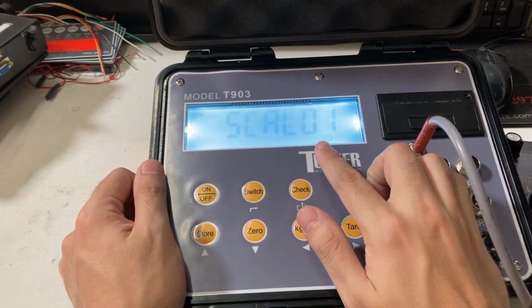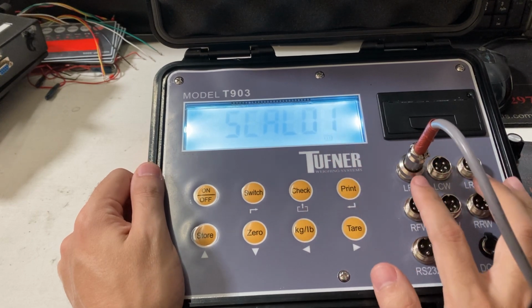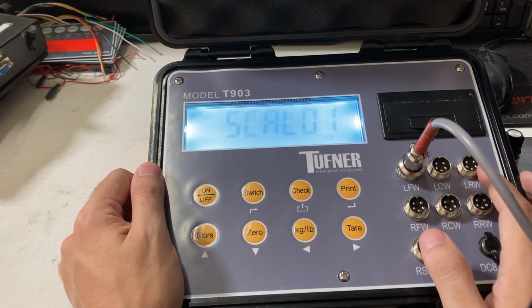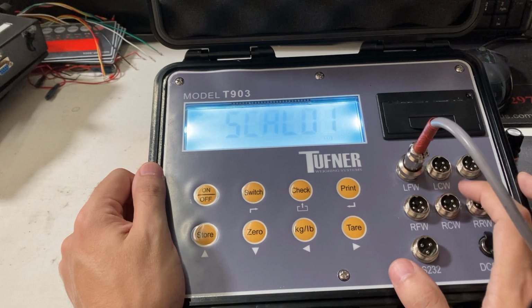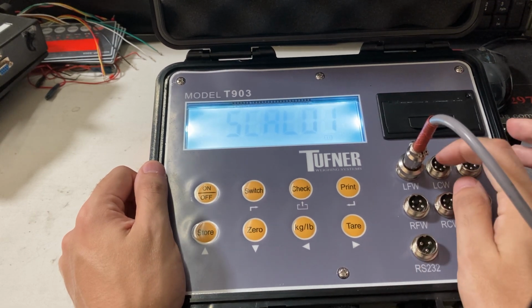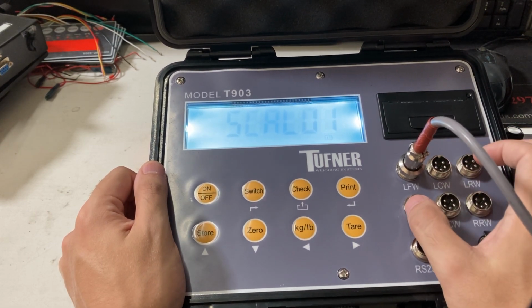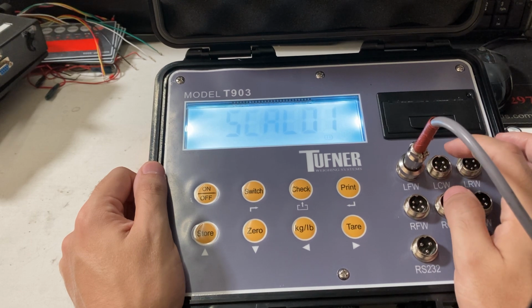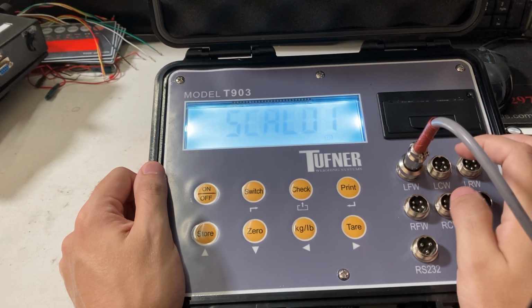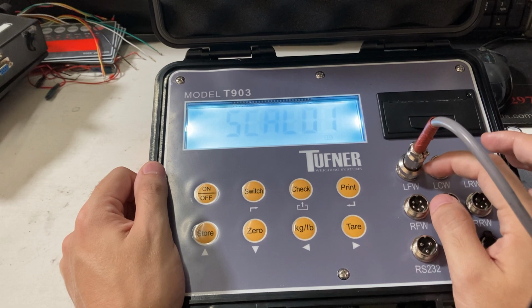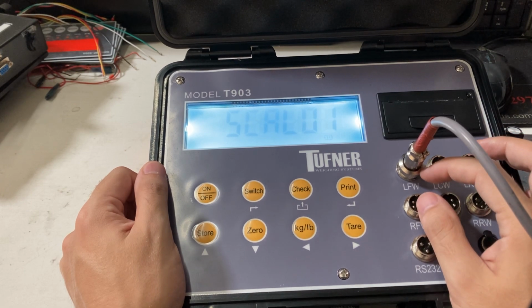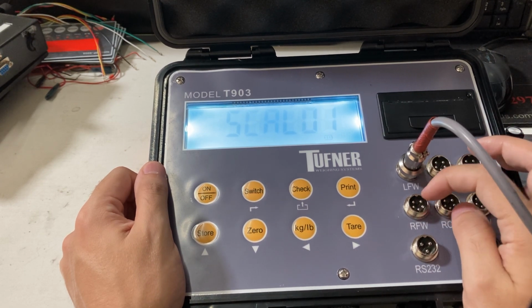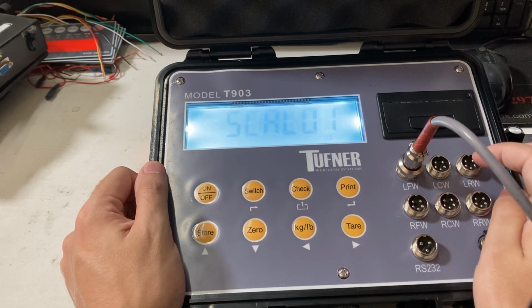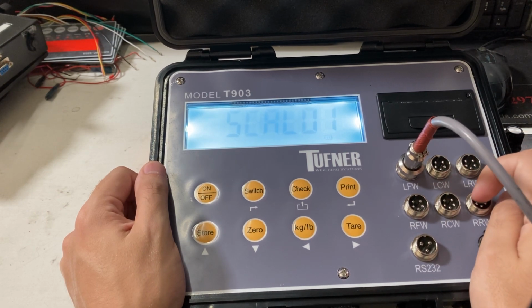So when you're calibrating, always calibrate in pairs. So calibrate LFW, RFW, LRW, and RRW, and LCW to RCW. So if you want to calibrate the last 2 pads, for example, and you have a 4-pad, you're gonna have to calibrate both 5 and 6. LCW, RCW. If you want to do 1, you want to do 1 and 2. Because if you don't, then the calibration on the first one might throw off the second one. And if you do just calibrate the third one, it might throw off the calibration on the second one.